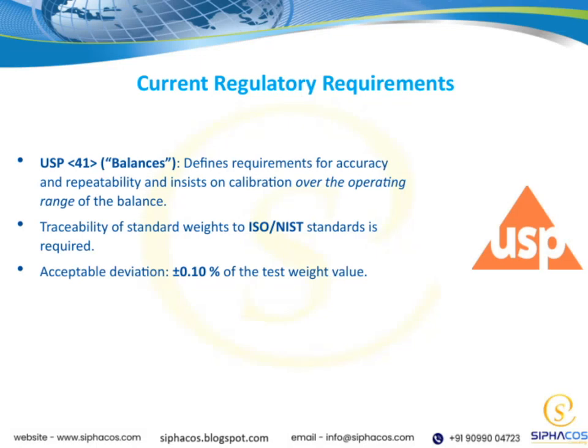Let's take a closer look at the current regulatory requirements outlined in USP 41 for balances. This section emphasizes the importance of accuracy and repeatability in weighing processes. It's crucial that balances are properly calibrated across their entire operating range to ensure reliable measurements. Calibration isn't just a one-time task. It needs to be performed regularly and over the full range of the balance to maintain confidence in the results.